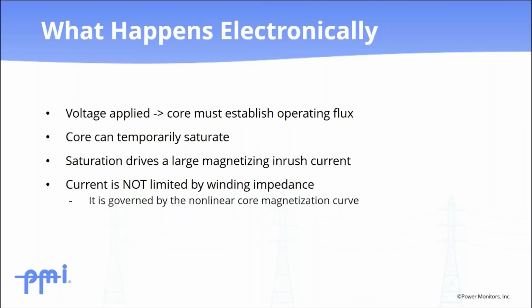Once the core saturates, the magnetizing current shoots up dramatically. And here's the important part. This current is not limited primarily by winding impedance the way normal load current is. Instead, it's governed by the nonlinear magnetization curve of the transformer core.